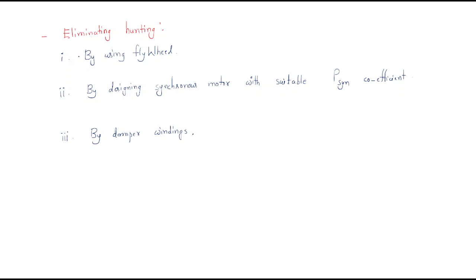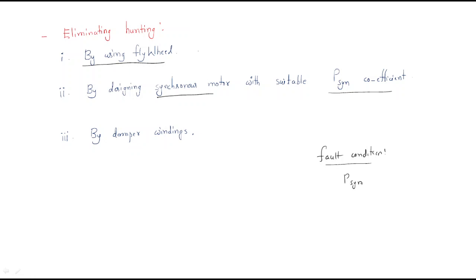To eliminate hunting, the first method is by using a flywheel, which is an important hunting-elimination application. The second method is by designing the synchronous motor with a suitable synchronizing power coefficient. In the fault condition, synchronizing power is developed, and by maintaining the proper synchronizing power coefficient, hunting can be controlled.